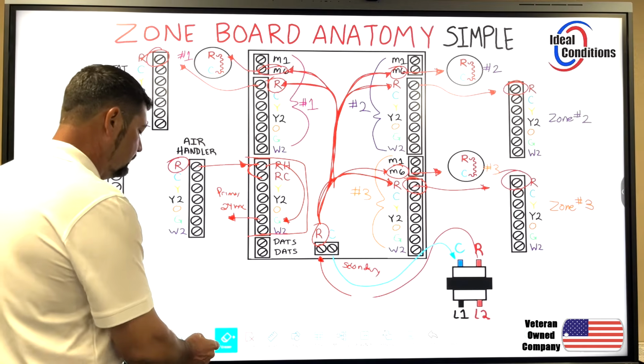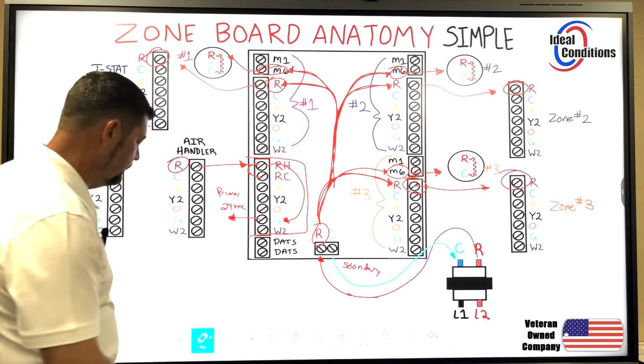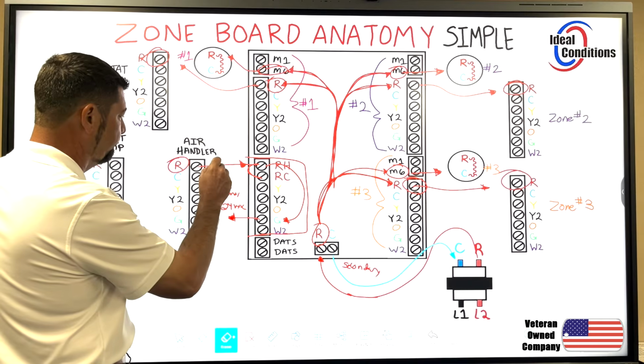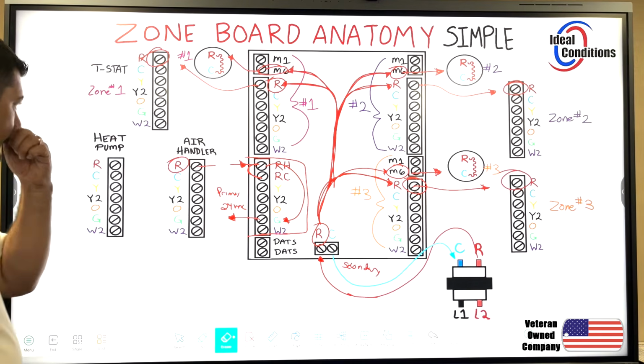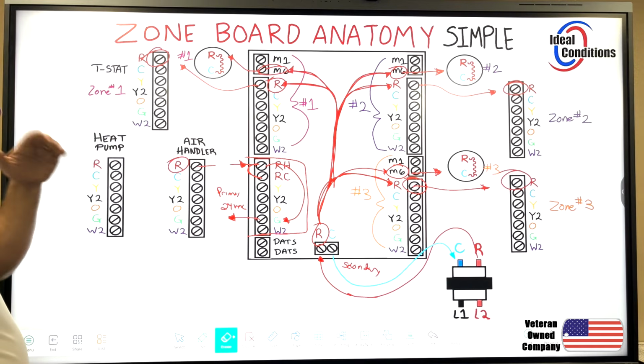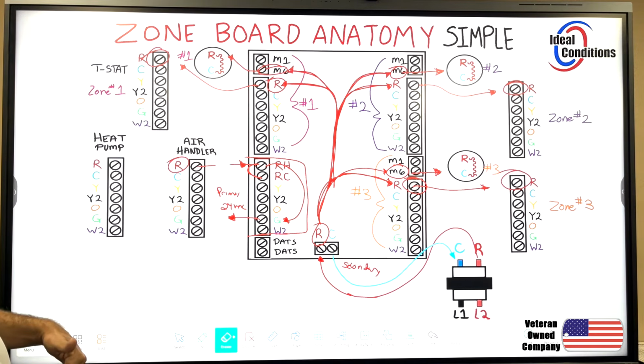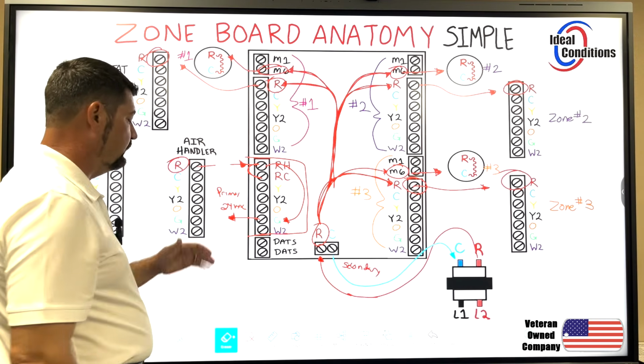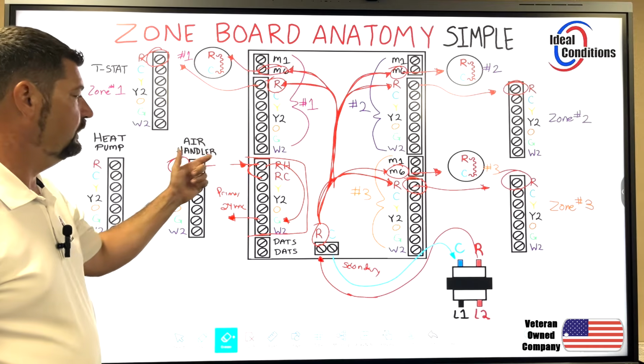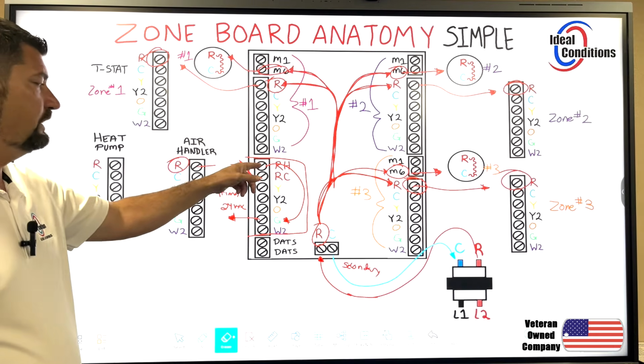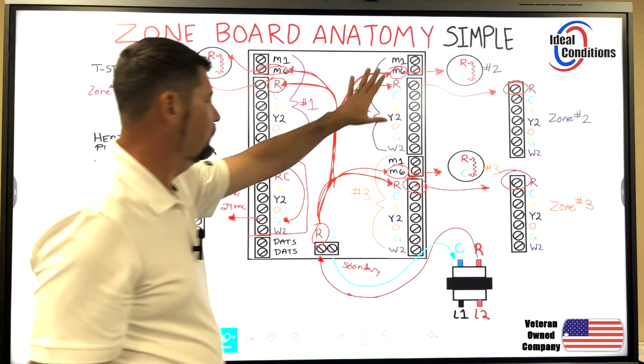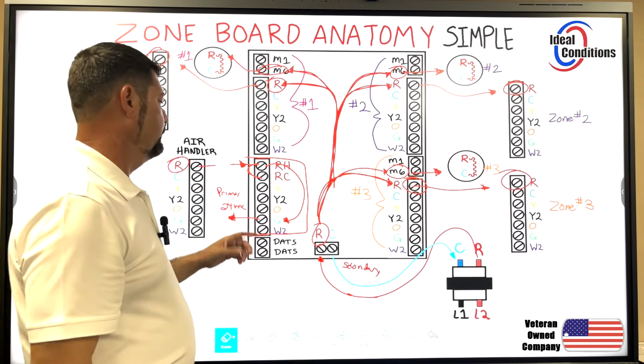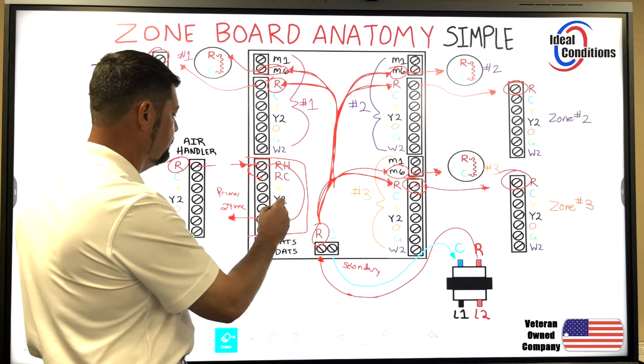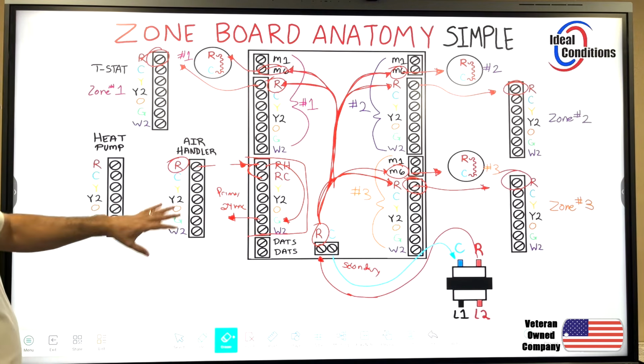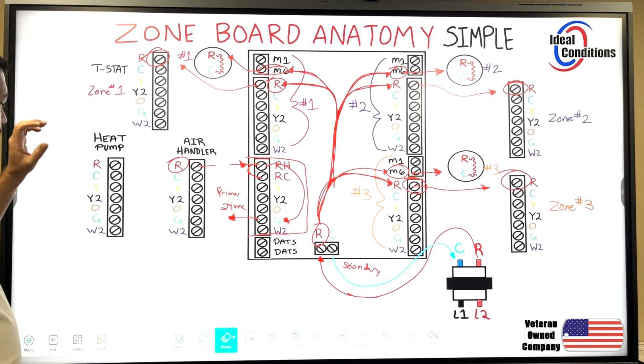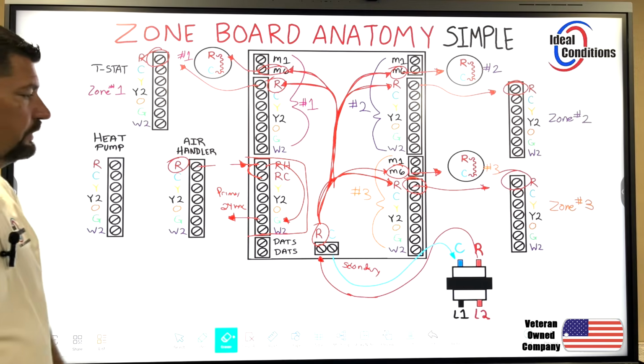Another way to shut the equipment down, and this is what happens a lot, is people will put a float switch here, coming out of the air handler, going to a float switch, obviously coming back up, and then as it leaves, if that float switch is tripped, you're not leaving with energy to go to that zone board. And if you don't have that 24 volts sitting there, then no matter what is going on here, they can all be calling, but your equipment can't relay the 24 volts to the corresponding terminals for those outputs to come back in internal and blower motors and run compressor contactors and reversing valves, right?